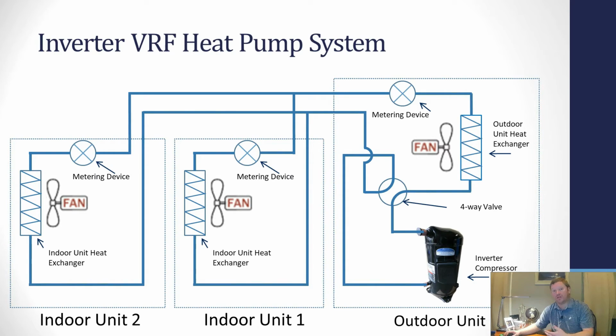With 1 degree, I keep everything running at a much lower speed, and we're doing something called maintaining. And you'll hear me in tons of videos say that the entire point of an inverter system is to maintain the set points. You never want to be recovering, because when you recover, especially with multiple zones, the compressor ramps up and somebody's going to be uncomfortable. Not to mention it's a lot harder for an inverter system to recover than it is to maintain, and consumes way more energy, and the list of problems goes on.